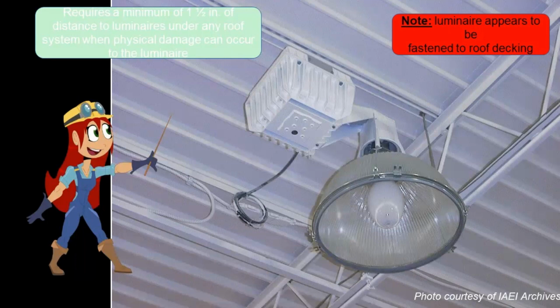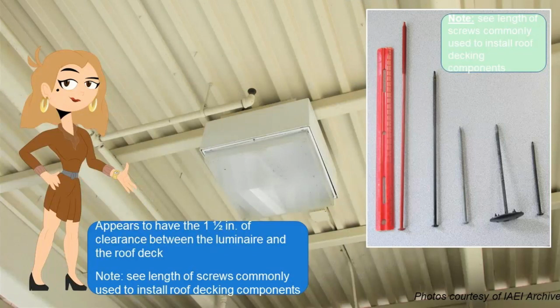Right, here's a good example. I do not have 1.5 inches from the roof decking down. So they just stuck a piece of unistrut up there above the joist and put the light there. A 1.5 inch screw could hit that ballast or light or a portion of that light. Or a long screw from, I would say, 1.5 inches. A long roof deck screw could hit and damage that light, cause problems. All right. Okay, so in this one, you could actually see some of the screws sticking down. You can see how far those things protrude. They're pretty long, and they can easily hit these lights. So probably a positive, good code change.